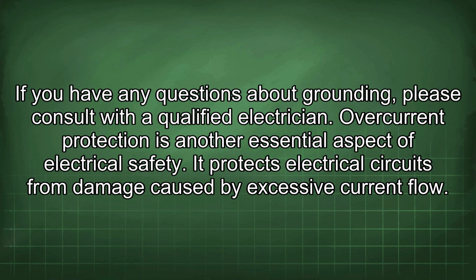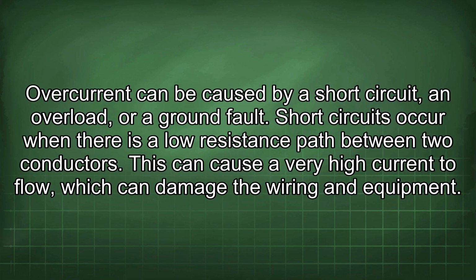Overcurrent protection is another essential aspect of electrical safety. It protects electrical circuits from damage caused by excessive current flow. Overcurrent can be caused by a short circuit, an overload, or a ground fault. Short circuits occur when there is a low resistance path between two conductors. This can cause a very high current to flow, which can damage the wiring and equipment.